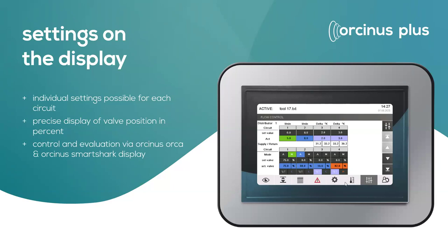And when you connect our Orcinus system to the TCU, then you can make the settings of the TCU as well. And if you have a pump which is not running at 100% or zero, then you can say to the pump, I have a green light, everything's perfect, so you only have to run at 60% or 70%, which saves a lot of energy.